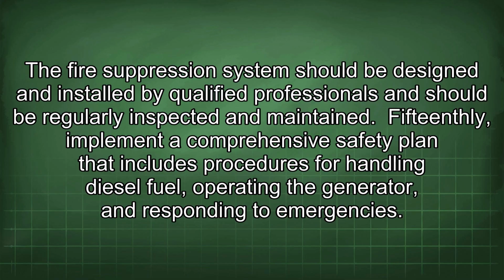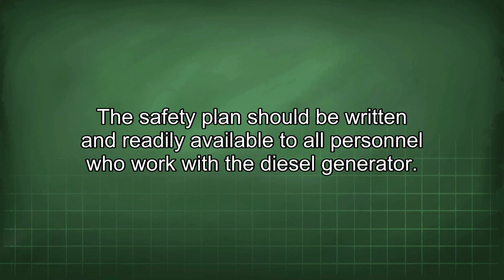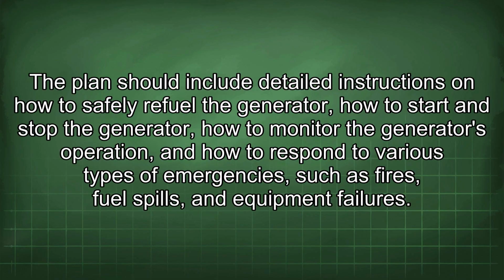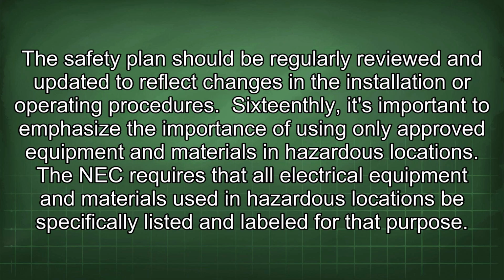15thly, implement a comprehensive safety plan that includes procedures for handling diesel fuel, operating the generator, and responding to emergencies. The safety plan should be written and readily available to all personnel who work with the diesel generator. The plan should include detailed instructions on how to safely refuel the generator, how to start and stop the generator, how to monitor the generator's operation, and how to respond to various types of emergencies such as fires, fuel spills, and equipment failures.